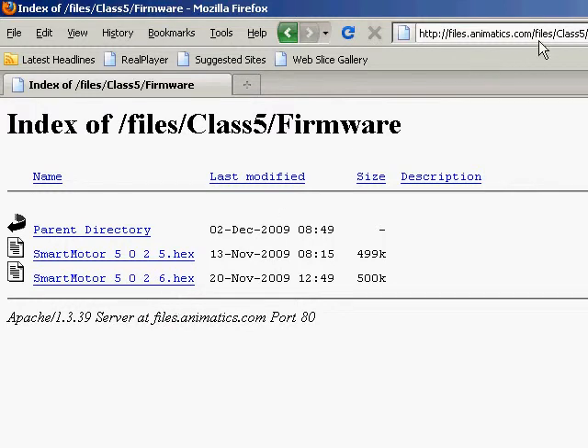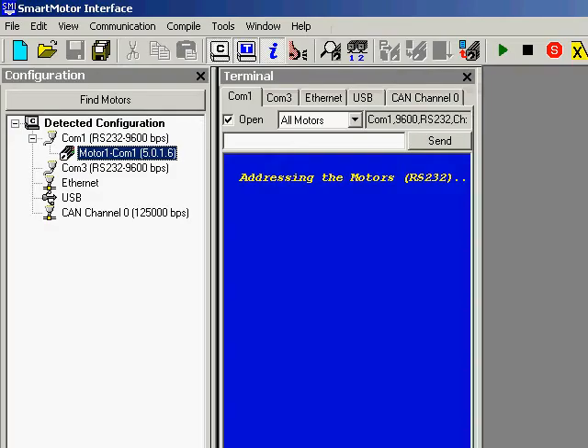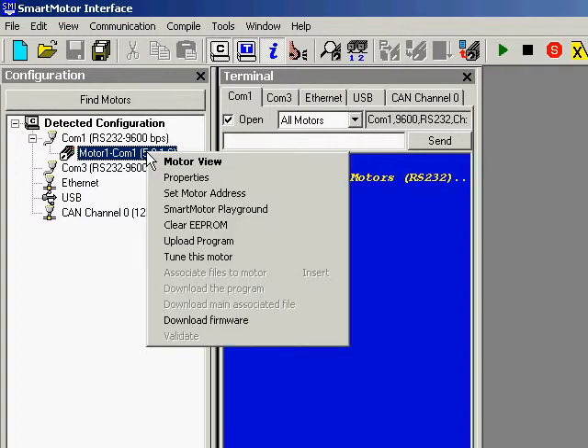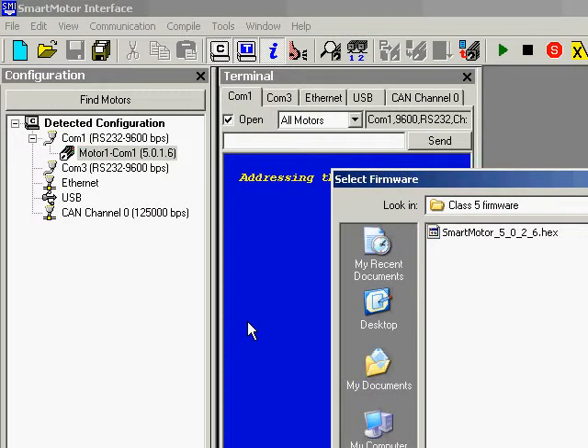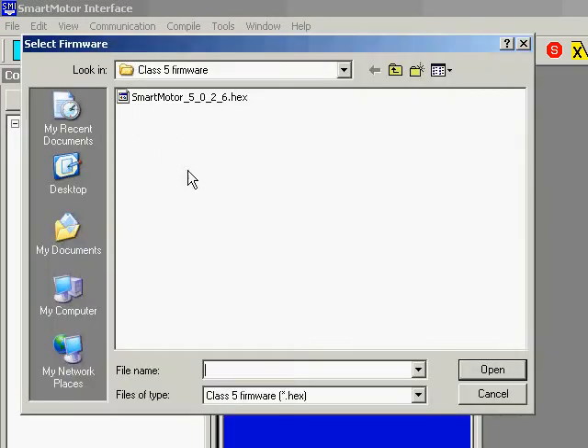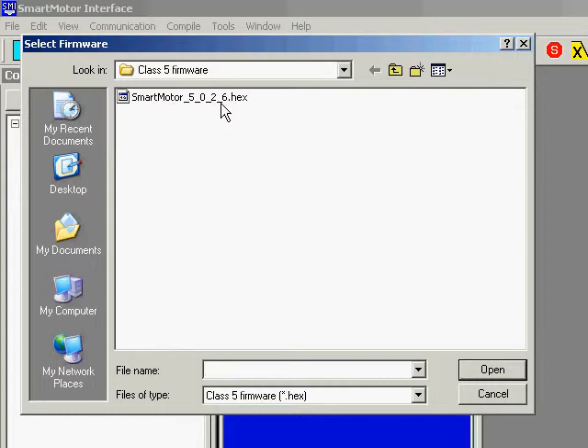Please save that file somewhere on your computer so we can download it. Right-click on the Smart Motor icon, and you'll have an option that says Download Firmware. You'll have to search and find the firmware file. It is a .hex and has the firmware version there, 5026.